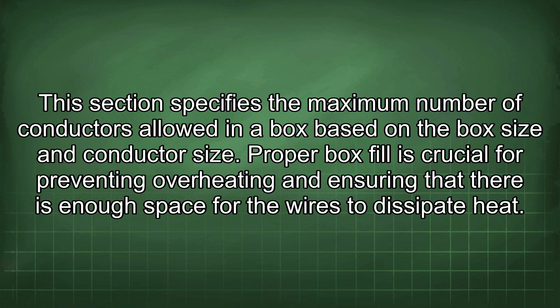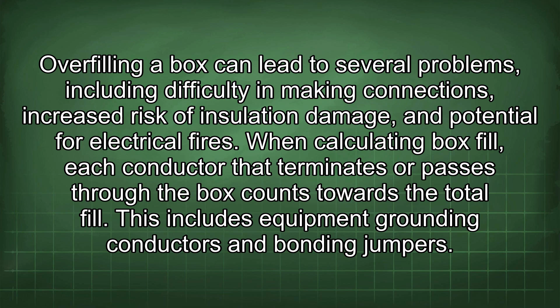potential for electrical fires. When calculating box fill, each conductor that terminates or passes through the box counts towards the total fill. This includes equipment grounding conductors and bonding jumpers. Certain devices, such as switches and receptacles, also count towards the box fill.